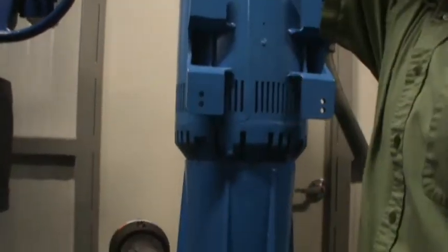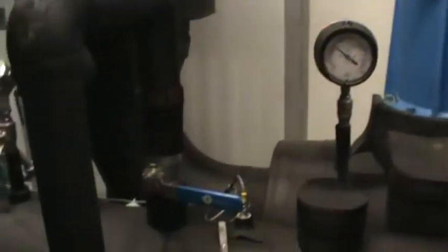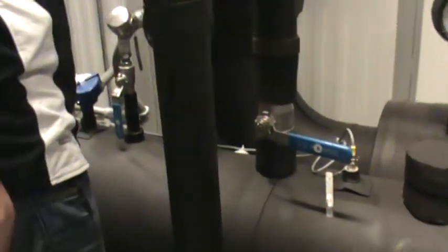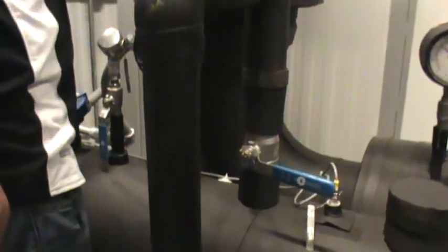It's identical on the other side for the condenser water. If you look, we use what's called Turck flow switches on these. There's all kinds of instrumentation available, but here we don't want the chiller to start and run if it doesn't have chill water flow. So a pump will start, and we wait to confirm that it sees water flow, and then we'll get the compressor started. You can see part of the one compressor circuit up there.